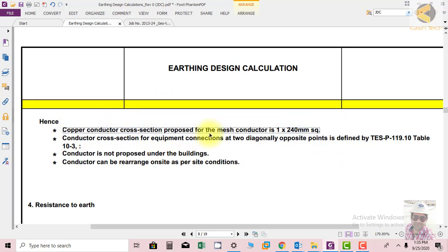Hence after getting these calculations we came to know that copper conductor cross section proposed for the mesh is 1 by 240 square mm. We have chosen this conductor. This is the cross section area of the conductor. Conductor cross section for equipment connections at two diagonally opposite points is defined by TESP table 10-3.